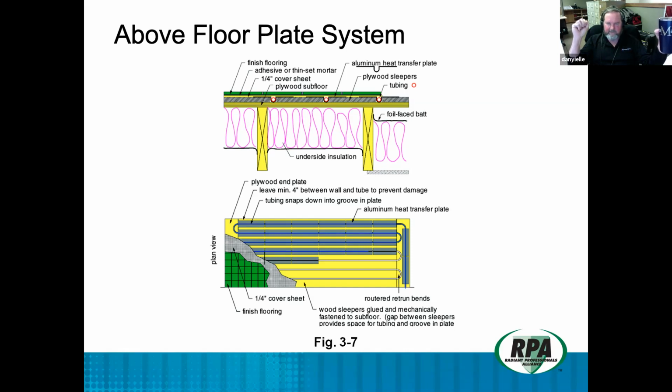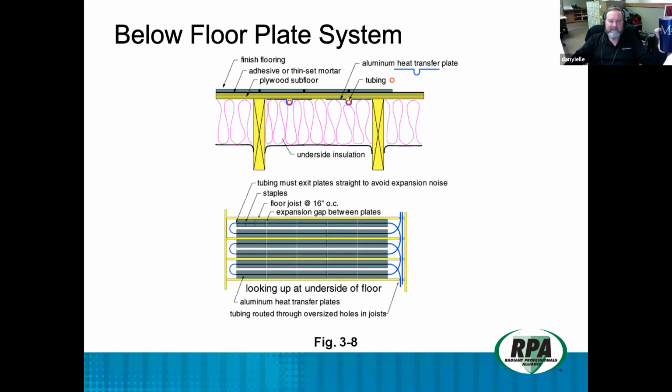But if you absolutely have to have pad and carpet, as thin and as dense a pad as possible, and as thin and as dense a carpet as possible. And there are actually radiant rated pads and radiant rated rugs that are available to accomplish and achieve that goal. So, it's tough to tell them what they can and can't do in their own home. But if they say, no, I'm going to cover the floor with carpet, then say, okay, I need your signature here in this contract acknowledging that I told you not to do this, so that when it's 10 below outside and your house won't go above 50, that we don't have to remember this conversation.